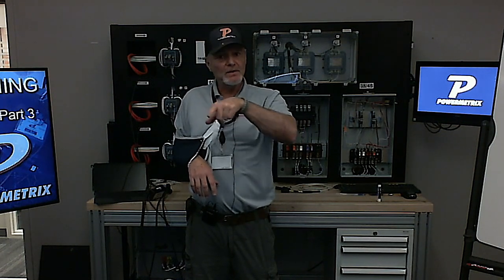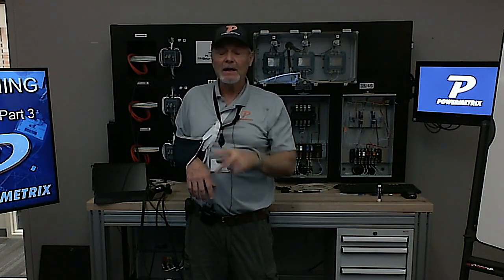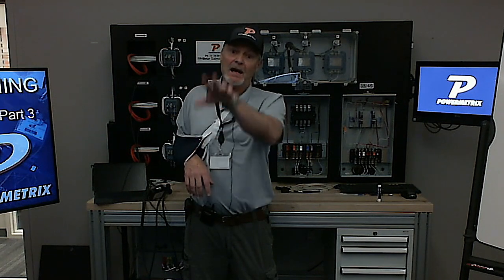But you can also use connect view on the equipment and actually look and see where your connections were. In the case we showed, you're connecting 3 voltages, 2 currents. So I do have a voltage connection, I just don't have either one of my current connections there. So because I don't have that, there's nothing there you can see on the test switch.